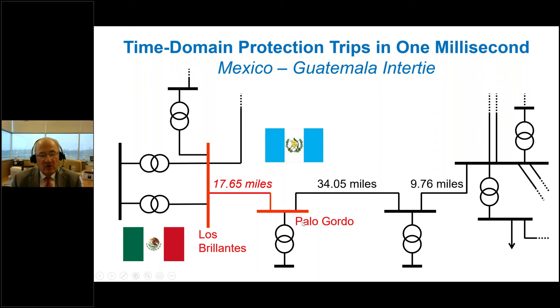And this line has some traveling wave protection equipment on it that SEL developed. And it trips in 1 millisecond, not 1 cycle, 1 millisecond. Let's take a look at this. You can see the pre-fault load currents are quite small. And so the intertie was lightly loaded, and then a fault occurred on phase C. You can also notice a fair amount of current transformer saturation that can affect traditional protection.